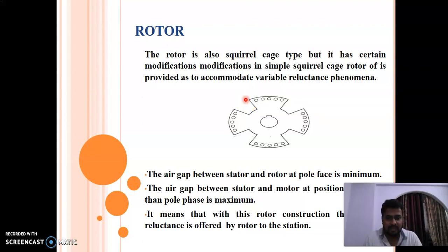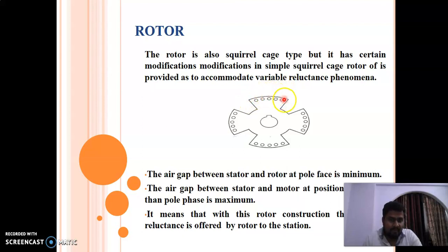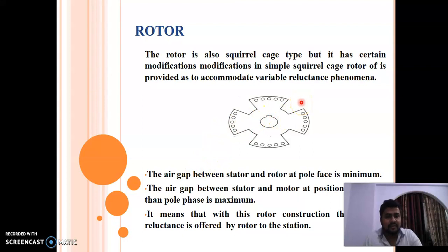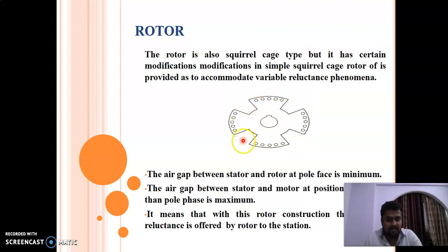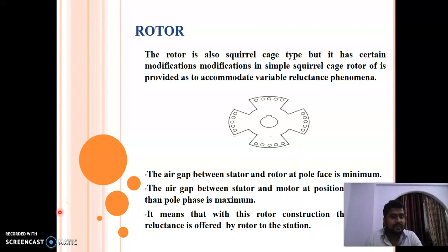The copper bars have been short-circuited by two end rings, similar to those used for a squirrel cage rotor. You can see that the air gap between stator and rotor at the pole face will be minimum, and the air gap between stator and rotor at the interpolar positions will be maximum. This means that with this rotor construction, variable reluctance is offered by the rotor to the stator, and these modifications accommodate the variable reluctance phenomena.